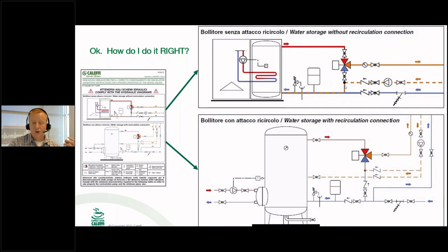And you'll notice here, it's just like what we did in that last picture where we gutted that swing check. So now it can go backwards through this cold inlet of the mixing valve, and then back to that domestic hot water source, and then back around to the mixing valve. And so again, you want it to be able to add heat to the loop because you don't want to have droop either. You want to maintain the temperature.